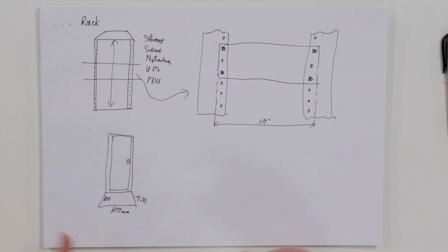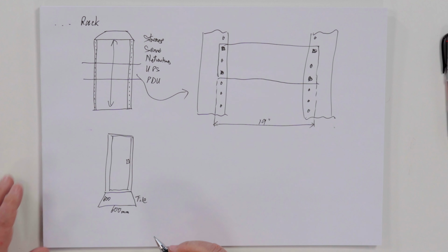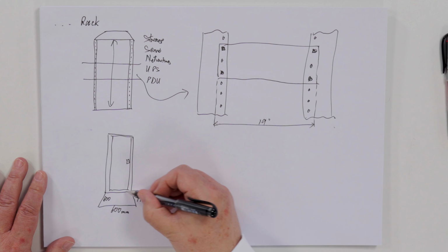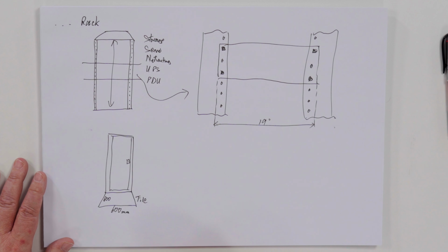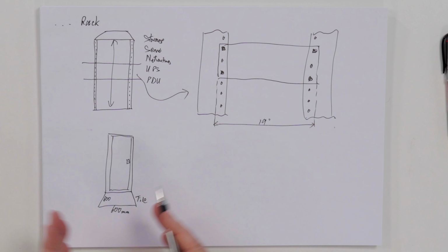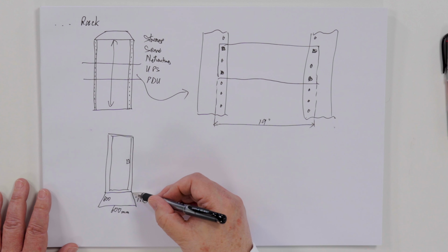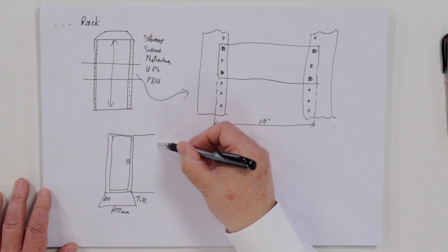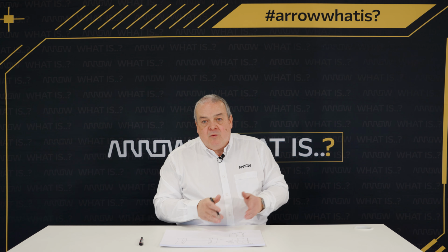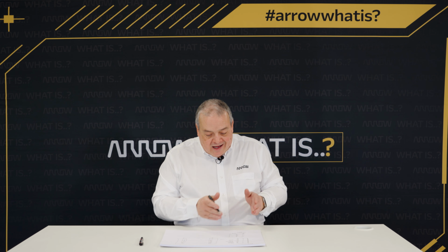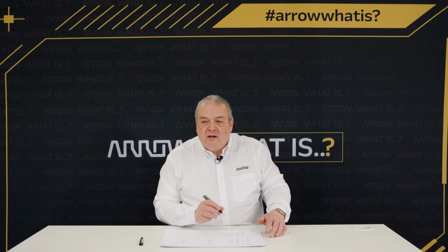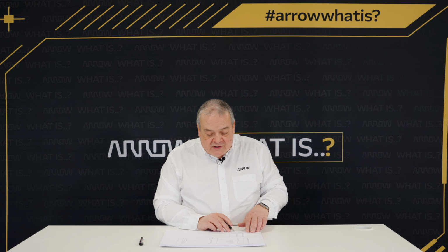This is where I say again, we keep flicking between metric and imperial. A 600mm tile and a standard 600mm rack means the rack fits perfectly on the width of the tile. This makes it very straightforward when putting multiple racks into a data center, because we know where the tile breaks are going to be, and the racking breaks will be very similar - exactly the same, in fact. So that's the size of the tiles.